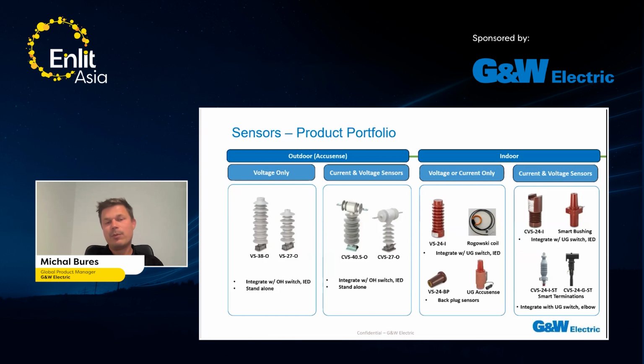So basically we can split the portfolio into two groups, outdoor and indoor sensors, as you can see on the screen. On the left side, you have the outdoor sensor, on the right side, the indoor sensors. You can easily recognize it by color, of course, because the outdoor sensor has an additional layer coat of silicon to better perform in the outdoor conditions. All of them are using the capacitive dividers and the Rogowski coils. Plus, as I already mentioned, we have active and passive variants almost for each sensor, almost.